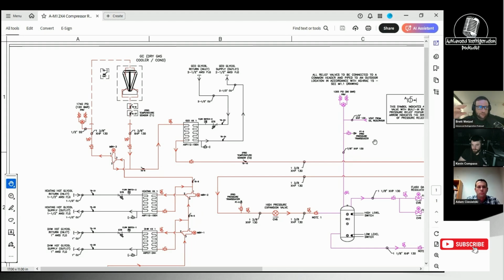And so essentially you have two PID loops fighting each other. You've got the gas cooler outlet being controlled for the TD control, but then you also have the HPV, which is using it for subcooling, but can never get a straight line. It's like trying to do superheat while you're trying to do an EPR, where it's not controlling pressure. It's just off of the temperature. So you never get a constant superheat, so you never get a constant flow. It's the same principle. You have two PID loops fighting each other, both trying to calculate off that gas cooler outlet temperature sensor.